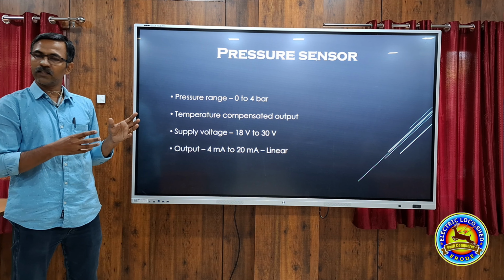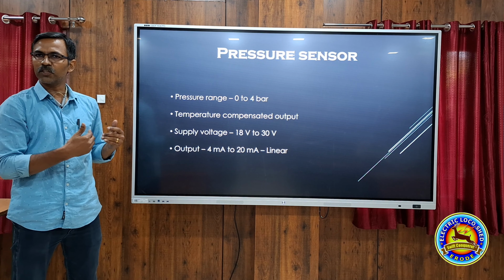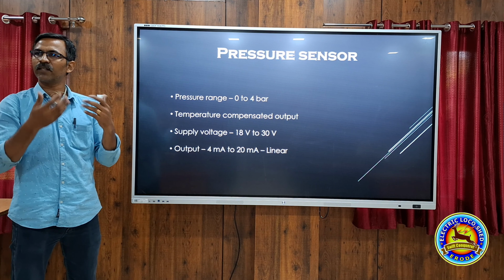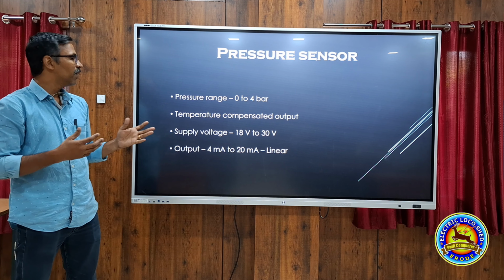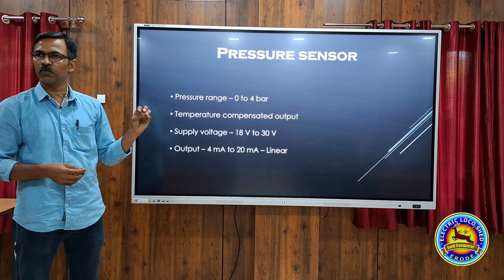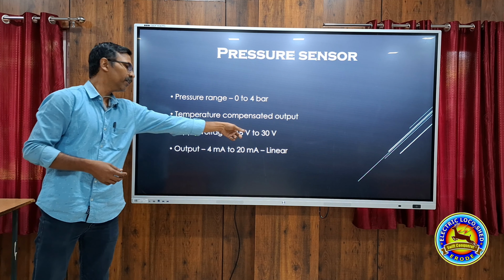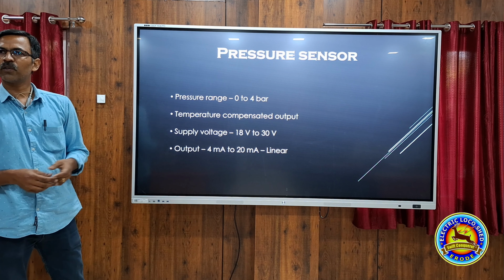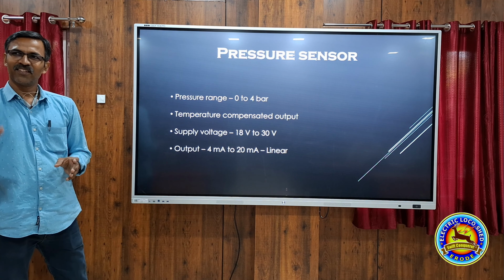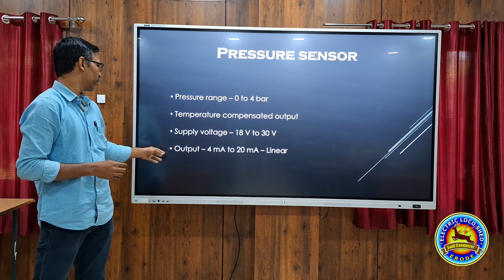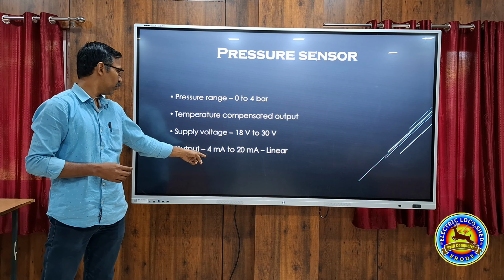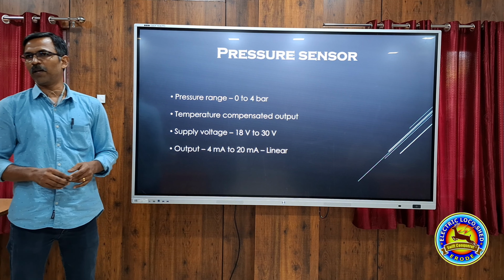The pressure sensor is connected in the transformer pipeline, so it will get heated up and cooled down over time. The output should not vary according to the temperature, so the outputs are temperature compensated. The supply voltage is 18 to 30 volts. For it to function, the supply should be within this range. In our loco, the supply is 24 volts. The output is 4 to 20 milliamperes.